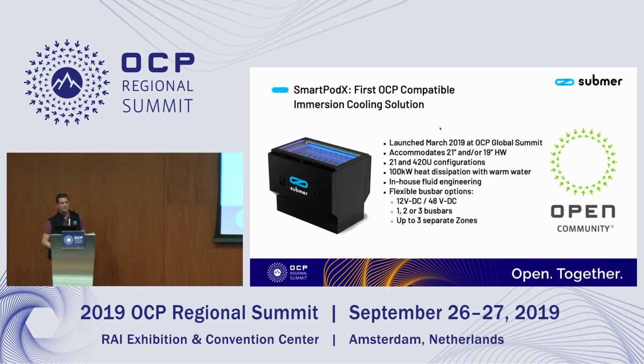Now, we presented back in March at the Open Compute Global Summit, the SmartPodX. This machine is an immersion cooling system which accommodates both 21-inch and 19-inch hardware. We build it in two form factors: a smaller one, 21 OpenU, and the 42 OpenU form factor, which essentially allows also to introduce additional redundancy in the system because we have more space.